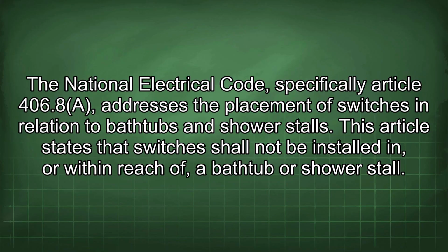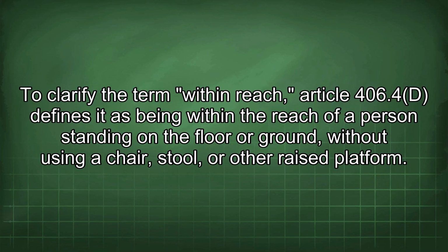The National Electrical Code, specifically Article 406.8a, addresses the placement of switches in relation to bathtubs and shower stalls. This article states that switches shall not be installed in, or within reach of, a bathtub or shower stall. To clarify the term within reach, Article 406.4d defines it as being within the reach of a person standing on the floor or ground, without using a chair, stool, or other raised platform.